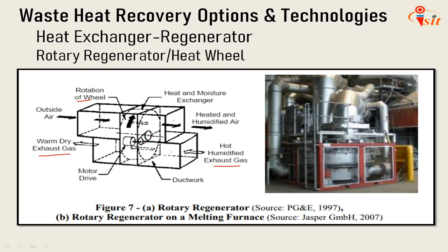One advantage of the heat wheel is that it can be designed to recover moisture as well as heat from clean gas streams. When designed with hygroscopic materials, moisture can be transferred from one duct to the other. This makes heat wheels particularly useful in air conditioning applications, where incoming hot humid air transfers heat and moisture to cold outgoing air. Besides its main application in space heating and air conditioning systems, heat wheels are also used to a limited extent in medium temperature applications. They have also been developed for high temperature furnace applications such as aluminum furnaces, though they are not widely implemented due to the cost. They are also occasionally used for recovery from boiler exhaust, but more economical recuperators and economizers are usually preferred.